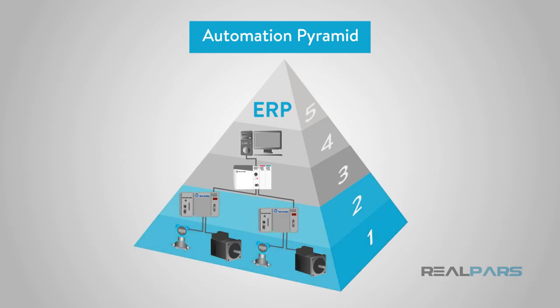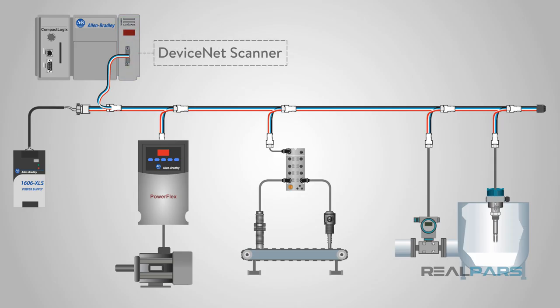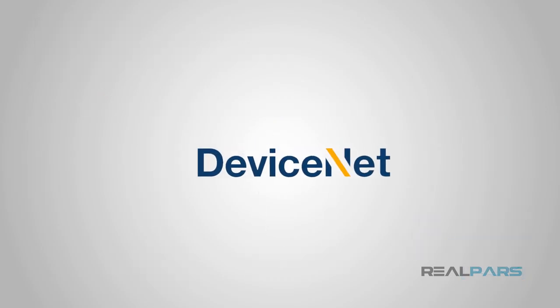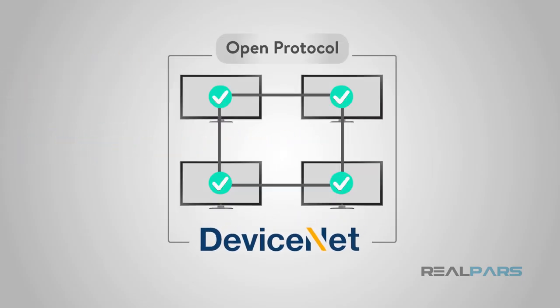DeviceNet is an application-level protocol used in the automation environment. It is a communication tool that allows you to logically talk between a PLC, or Programmable Logic Controller, and many control devices such as motors, conveyors, flow meters, level sensors, etc. Instead of the PLC talking directly to discrete I/O modules, it talks via a DeviceNet scanner. It was originally developed by Allen-Bradley, a Rockwell Automation brand, and they decided to share this new technology with others and make it an open network.